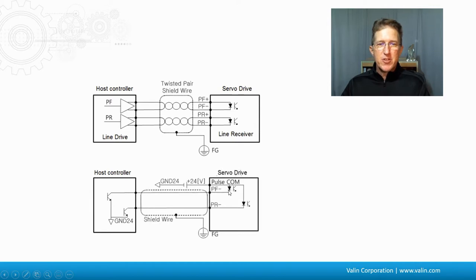If we look at that same circuitry, in the case of this drive, this can be pulled up to 24 volts here. That's a 24-volt power supply. Therefore, it's just pulled to ground at the controller. It's single-ended. It's going to be a little more prone to electrical noise, but it can work as long as you don't have that electrical noise.